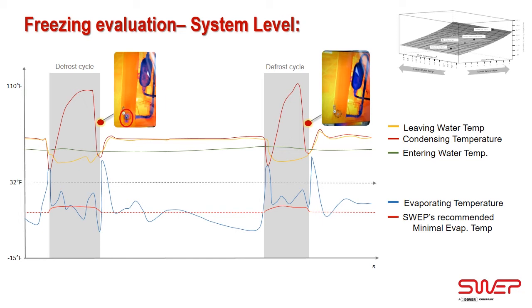The visual freeze detection method is the two pictures which you can see on the top part of this slide. If you look at the first defrost cycle, the dark spot inside the red circle is a visual freezing indication. Now, if we compare at the bottom of this slide the evaporating temperature curve, which is in blue, with SWEP recommended minimal evaporating temperature in red, what we can see is for the first defrost cycle, the evaporating temperature is getting below SWEP recommendation, and we were also able to detect a visual freeze indication. For the second defrost cycle, the evaporating temperature gets close to SWEP recommendation, but never below it. Also, we haven't been able to find any visual freezing indication for this cycle. So, after some additional qualification tests, our customer has decided to implement SWEP recommended minimal evaporating temperature into their control strategy. And now, based on it, they are able to counteract in cases where the evaporating temperature gets close to the freezing boundary of the system.